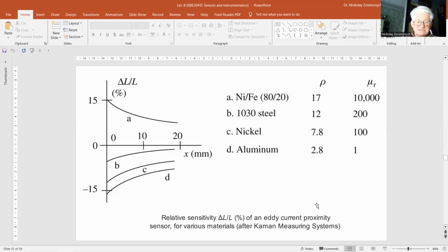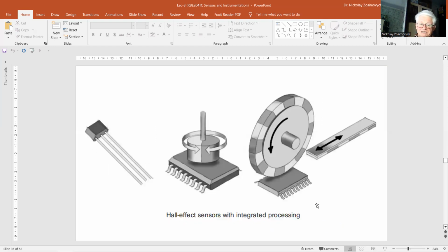As discussed previously in the section on resistive sensing, AMR sensors are frequently used to detect rotation and translation, usually in all robotic applications, using a combination of static magnets and sensors. Also, the sensitivity and linearity of Hall effect sensors is essentially small. Advancements in designing integrated versions, combining sensing, conditioning, calibration, and communication in a single chip, have turned the Hall effect position sensor into a viable alternative on the market.